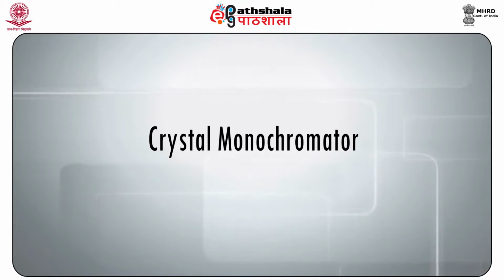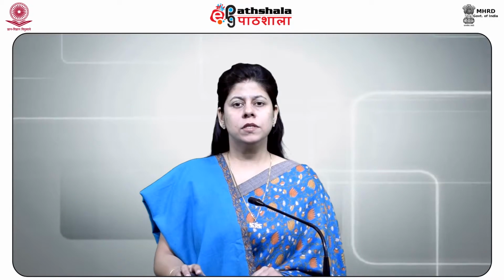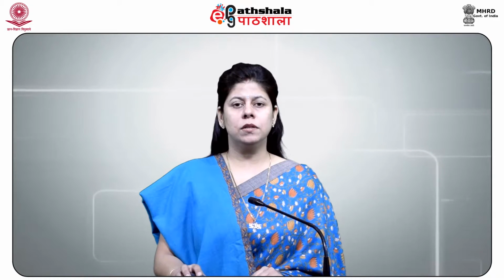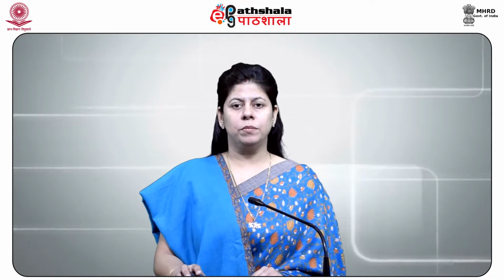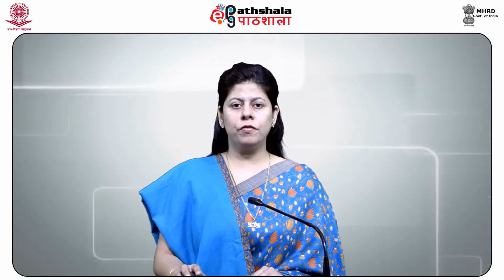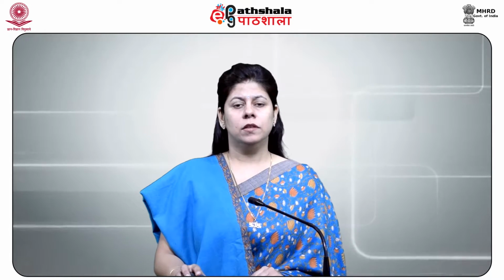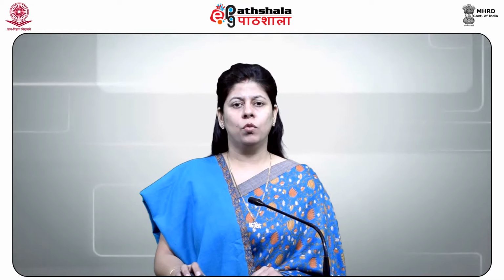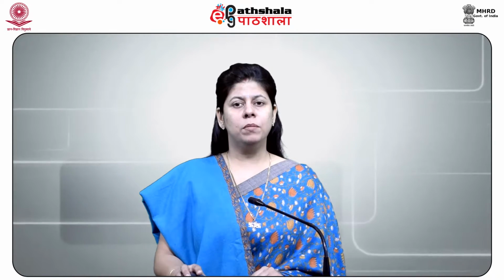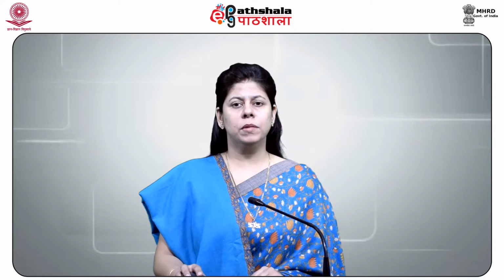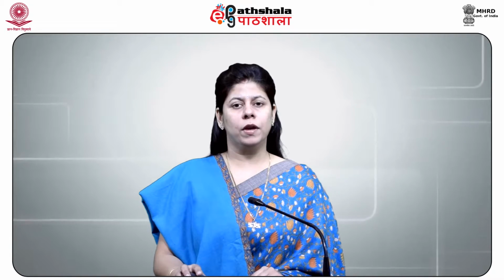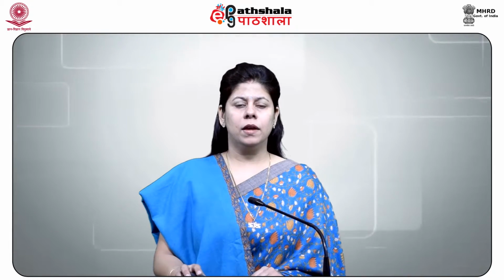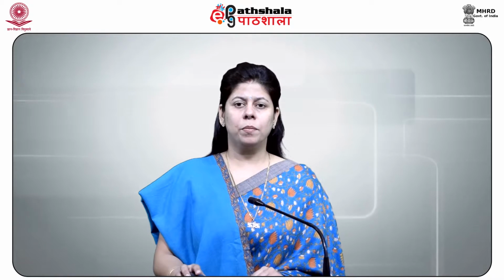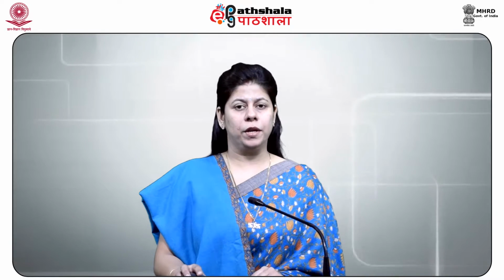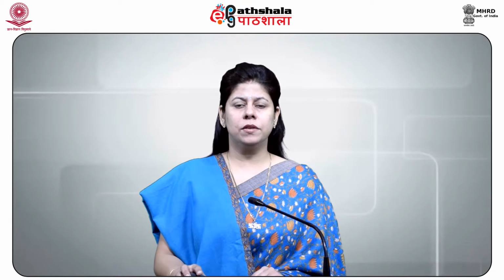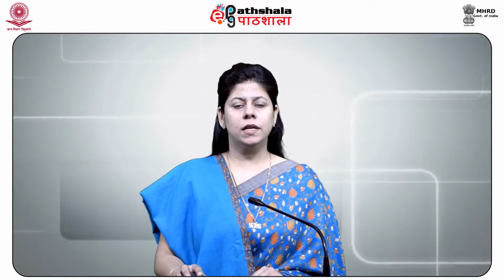The next is crystal monochromator. A crystal monochromator is positioned in the path of X-ray beam so that the angle of reflecting plane satisfies the Bragg's equation for the required wavelength. The beam is split up by the crystalline material into the component wavelengths in a similar way as a prism splits up the white light into a rainbow. Such a crystalline material is called an analyzing crystal.